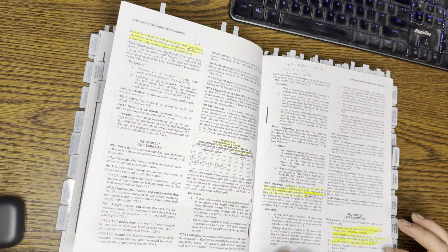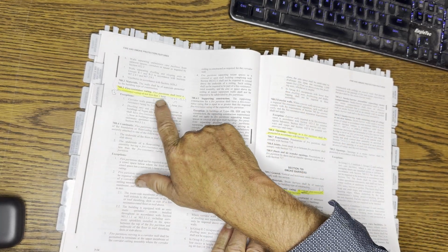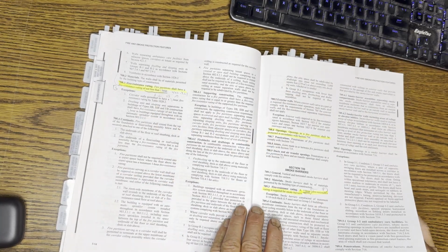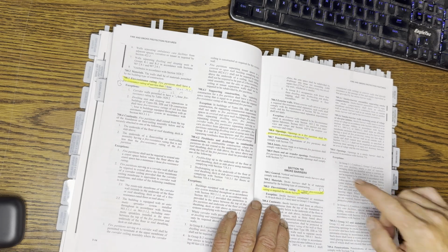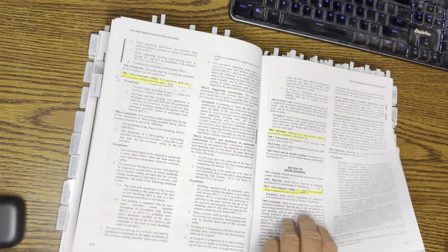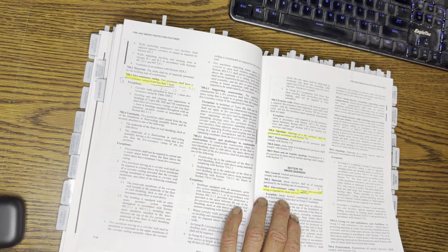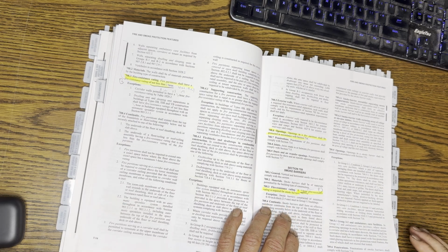Then you have fire partitions. They just have different definitions; fire rating is always not less than 1 hour for fire partitions. And then you have smoke barrier. It has to be 1 hour for fire rating. Let me explain what 1 hour means. It's based on ASTM E119. It's the furnace test.